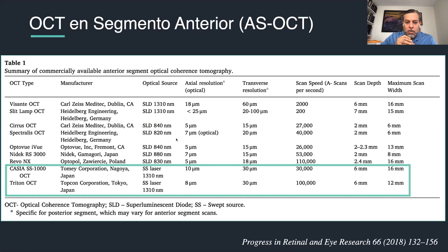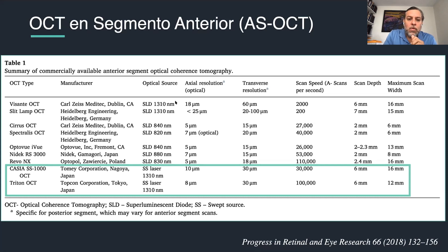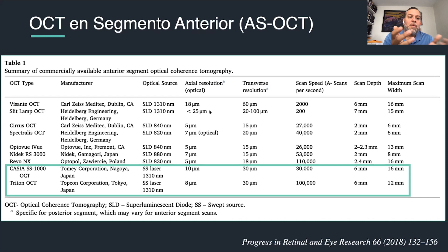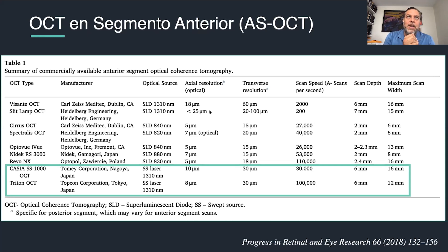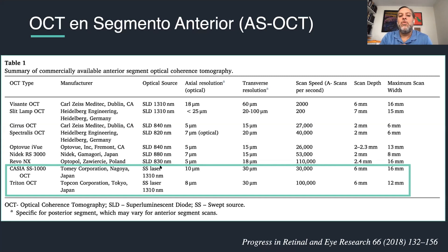When you're doing OCT on the posterior segment, you usually work around 840 or 820 nanometers. This is because retinal tissue and choroid don't have as much liquid consistency as the cornea or anterior segment. When imaging the anterior segment, you need a deeper wavelength. A second reason for needing a bigger wavelength in anterior segment OCT is that you want to penetrate opaque media — for example, to see the vertex of the angle beneath the sclera.